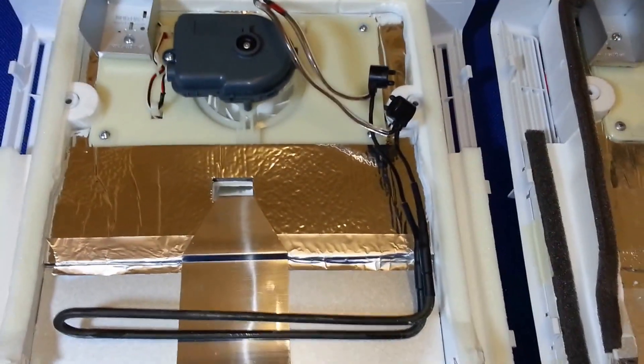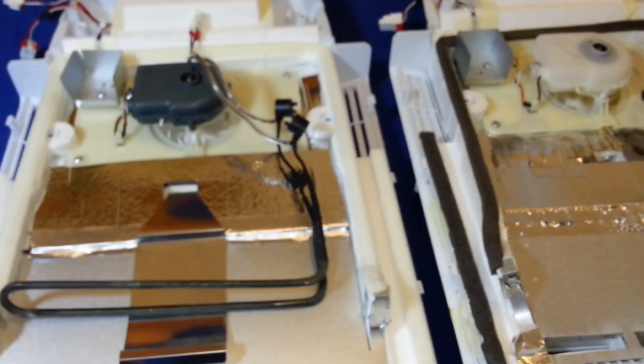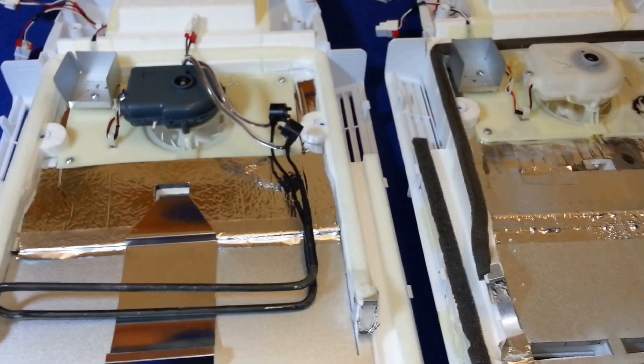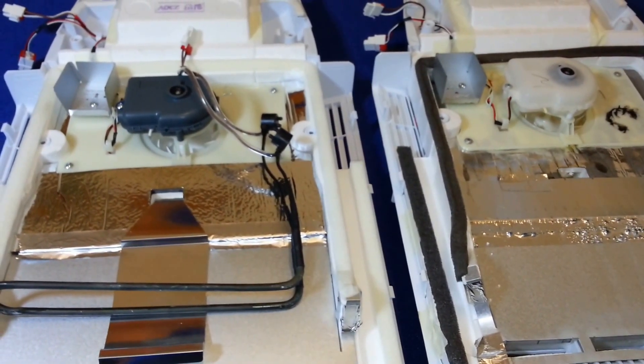There is an odd occasion where the actual defrost element could also fail on the appliance, causing slightly similar problems, i.e. ice build up. But we experienced maybe one in a hundred with a faulty defrost element.